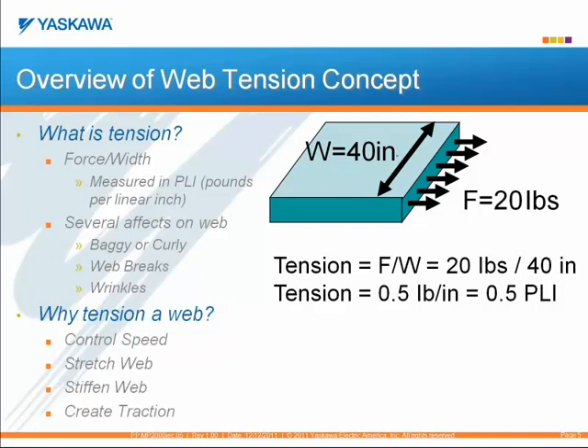Why tension a web? Four main reasons include: one, controlling the speed of the web during acceleration, steady state, and deceleration; two, controlling the web stretch to pull out any bagginess without damaging the web; three, to stiffen the web to reduce any sagging or wrinkles; and four, to create traction on the rollers — and then winding rollers to control slip, scratching, and tracking. Tension control elements include tension sensors such as load cells or transducers, a dancer, a tension actuator, and a tension controller — be it a TLC, a motion controller, or drive.